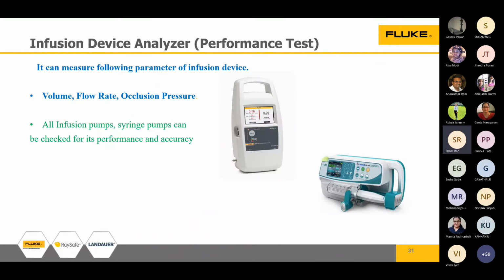Infusion device analyzer. We have an analyzer. You can check the infusion machine. Like on the right side, I have mentioned this is an image of a hospital infusion pump, and this is our instrument to test it. What can you do? Volume, flow rate. As I said in the previous slide, that protocol will be the same, the standard will be the same. Only you have to follow. These parameters should be accurate. These parameters should be within the permissible limits. Volume, flow rate, occlusion pressure.